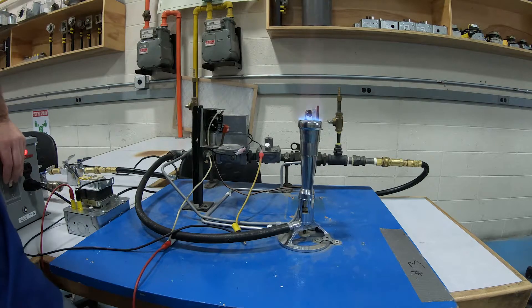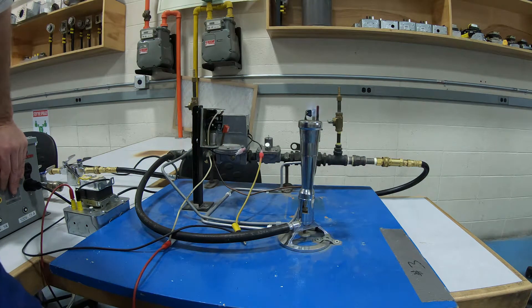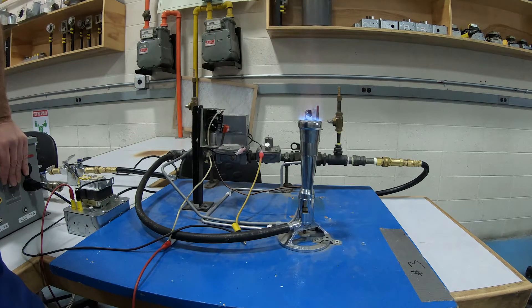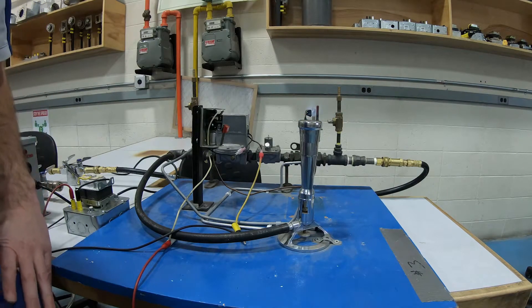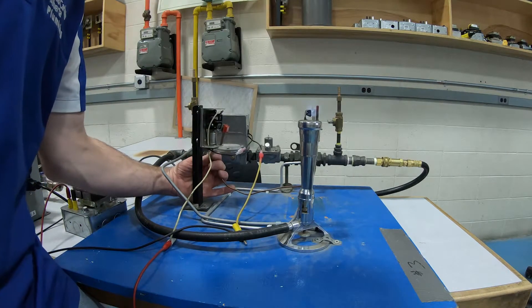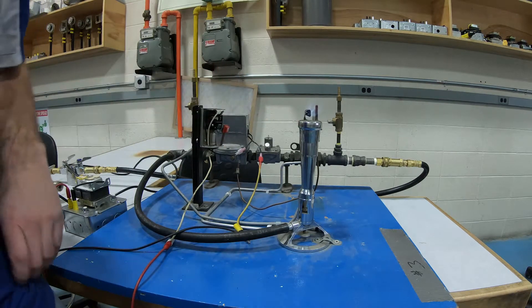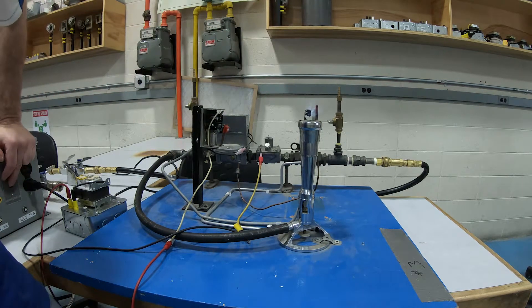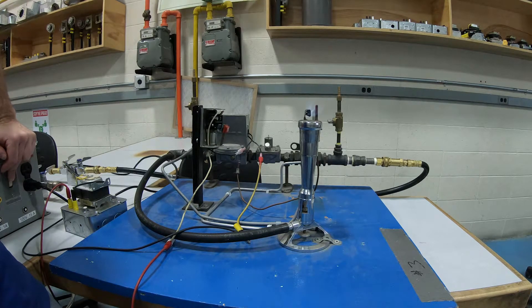Now, you might have noticed a flame shooting out of this tube right here. I'm not going to get my fingers too close. That is actually hot. That flame is from the diaphragm gas valve. It's called a bleed tube. It does that every time we use the valve. All right, let's simulate a problem. I just disconnected the thermocouple. Notice how our flame is still burning. But will this fire up the main burner? Nope. Won't do it. So that is a pilot switch in action.